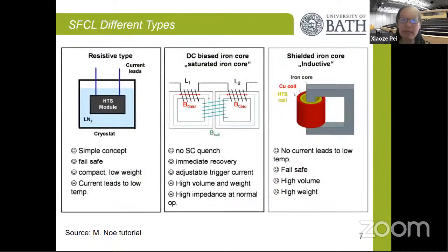And what are the main types of superconducting fault current limiter? The first type, which I'm going to focus on today, is the resistive type superconducting fault current limiter. This directly uses the superconducting characteristic. When the current in the superconducting tape is low, the tape maintains its superconducting state, which means there are no losses for DC condition, and very low AC losses.